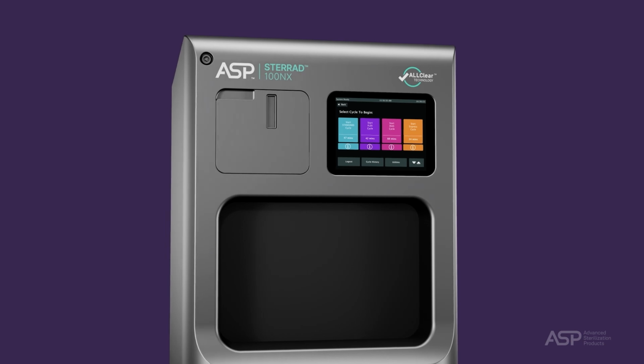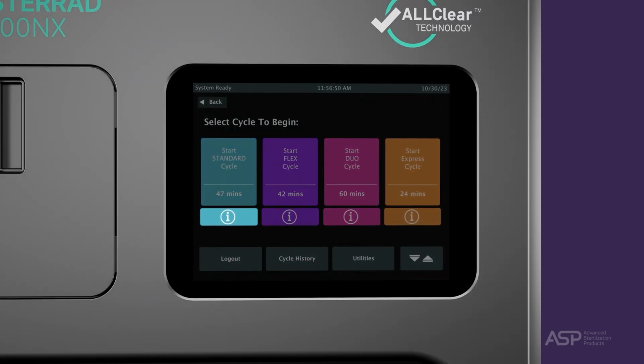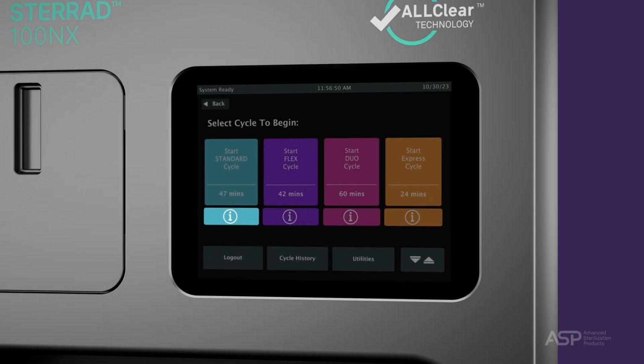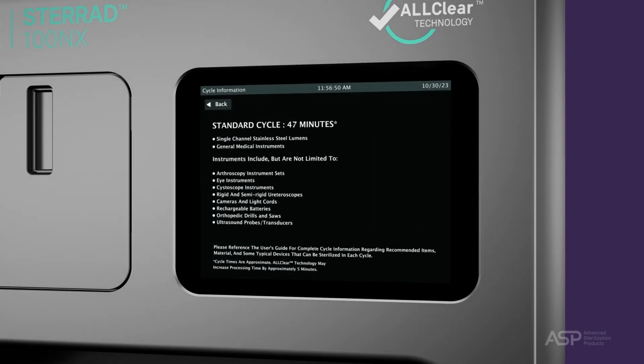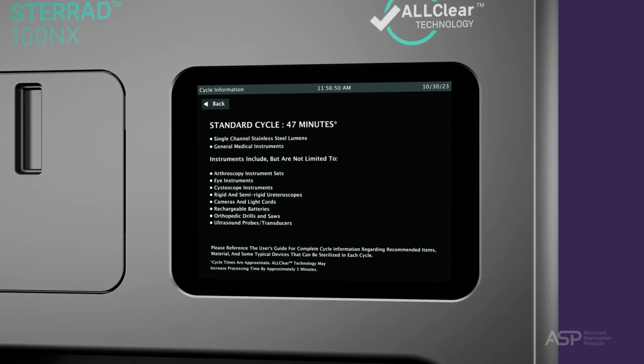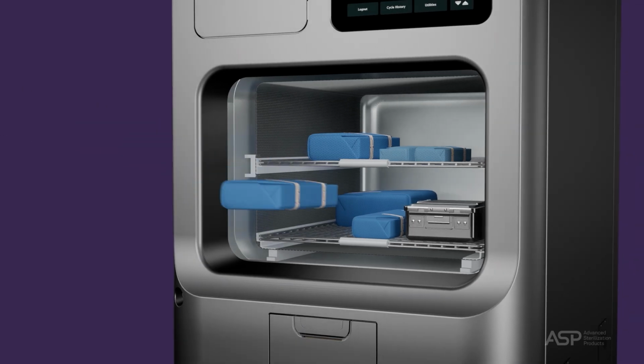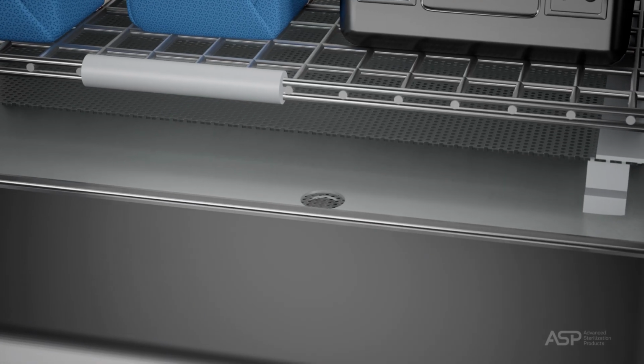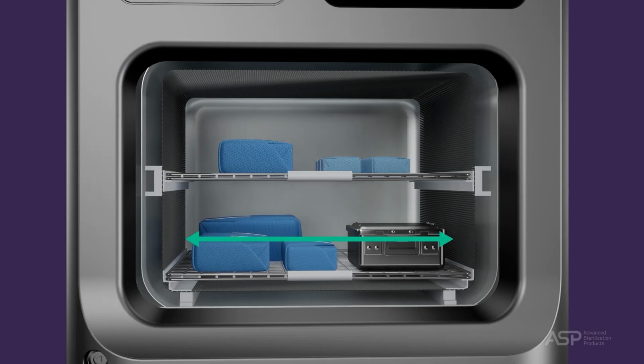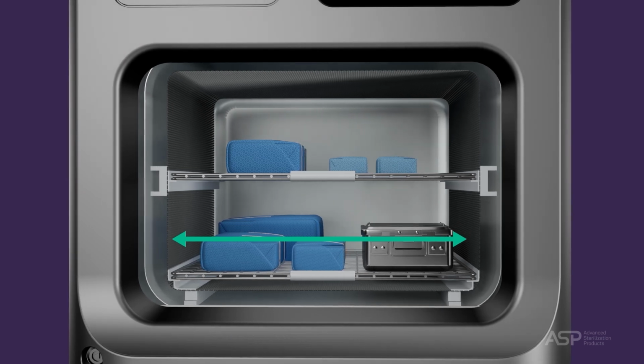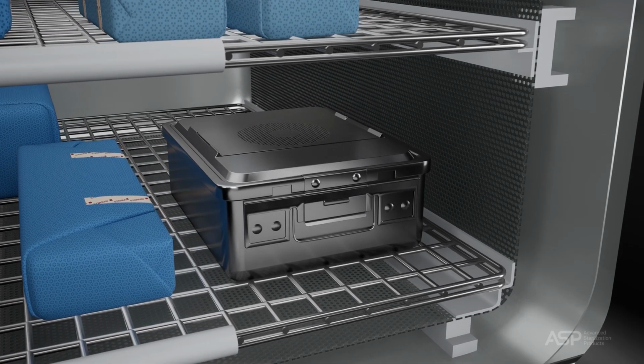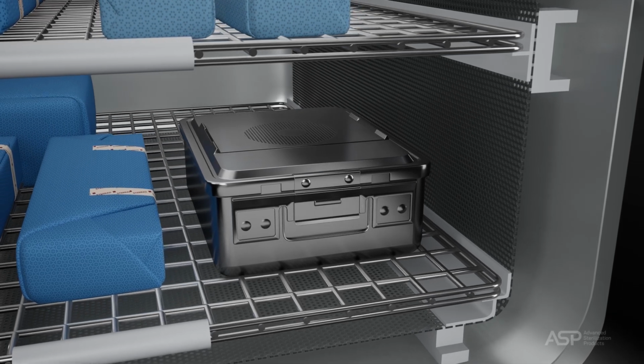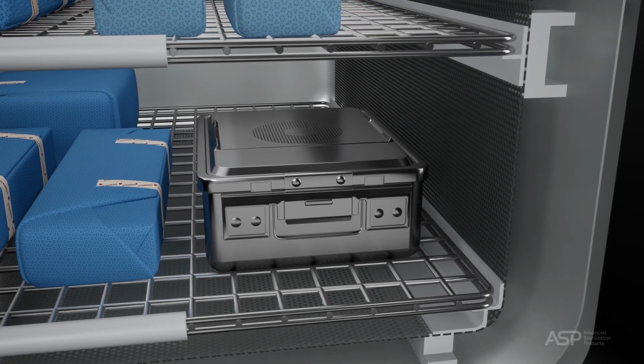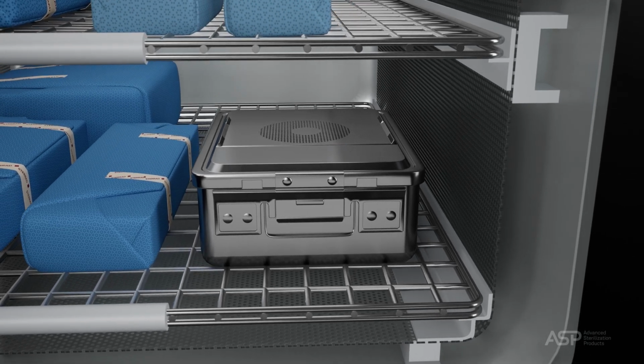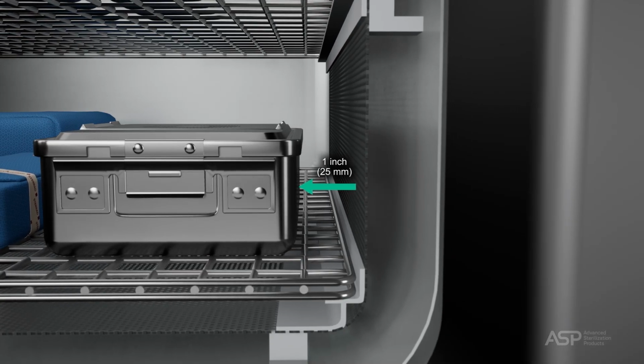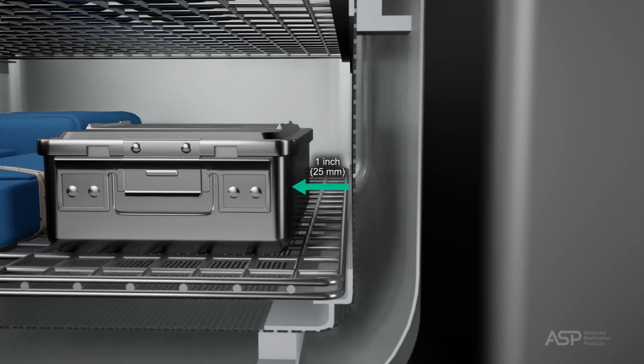You can obtain additional cycle information by pressing the information icon at the bottom of the cycle on your STERRAD 100NX Sterilizer with ALLClear technology ready screen. The screen will display information about the cycle and a list of items that can be sterilized in the selected cycle. When placing the load on the shelves, do not block the ultraviolet lamp beam in the front right side of the chamber. Ensure the load is centered on the shelves and that the shelves are centered in the chamber. Do not allow metal objects to come into contact with the walls of the chamber, the door, or the electrode. Contact with the walls, door, or electrode can cause a cycle cancellation and/or damage the item or the sterilizer. Leave at least 1 inch or 25 millimeters of free space between the load and the electrode.